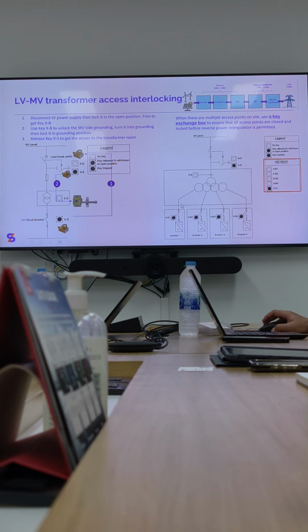This one will be on the inverter side, on solar. So first you isolate all the inverters on the breaker side, go to the key exchange box to exchange for key X0. X0 goes to the MV panel, isolate, and then take out the access key. With the access key, go into the control room. So we know the bottom side is isolated and safe, the MV side is isolated and safe, then do the maintenance.